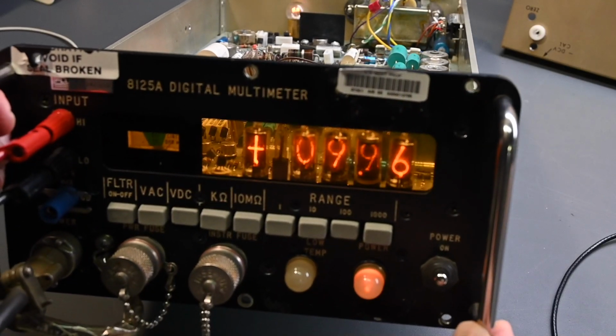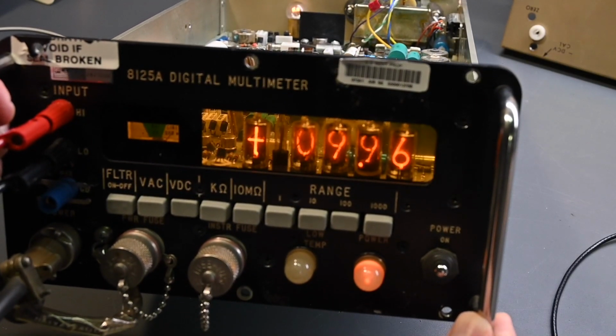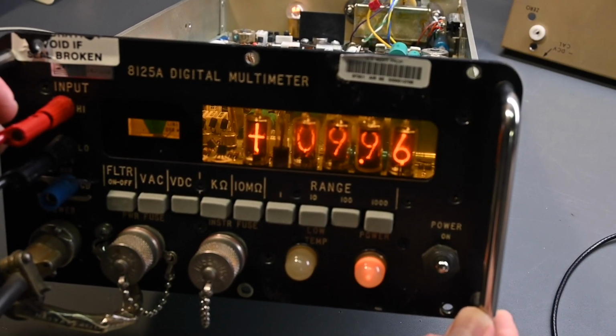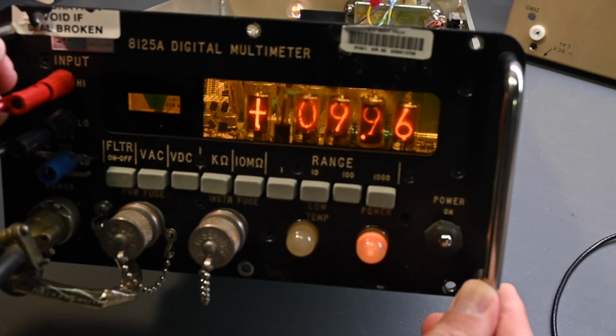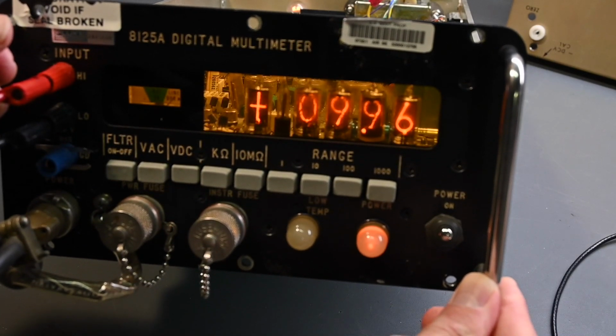So there you go, 9.96 volts. Again, I have 10 volts connected, so very, very close on the reading. Just some calibration would bring that right into spec.